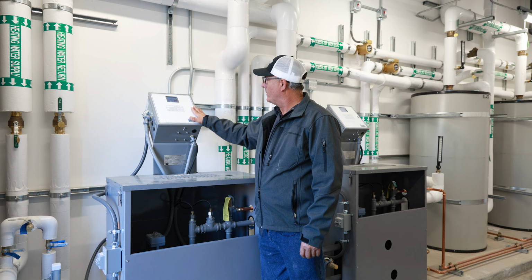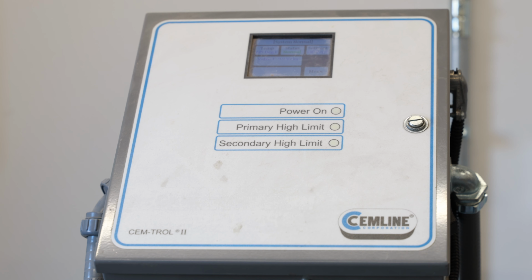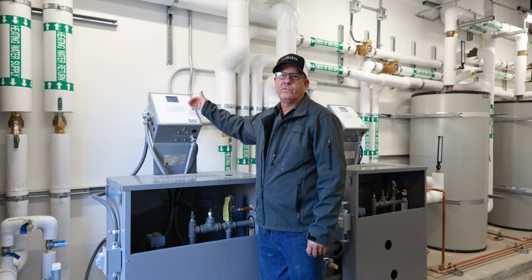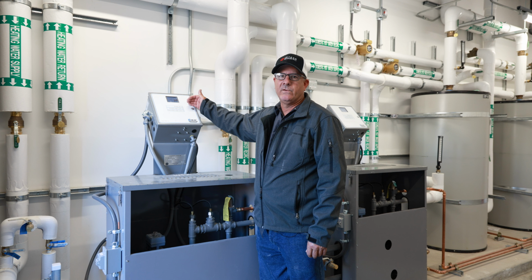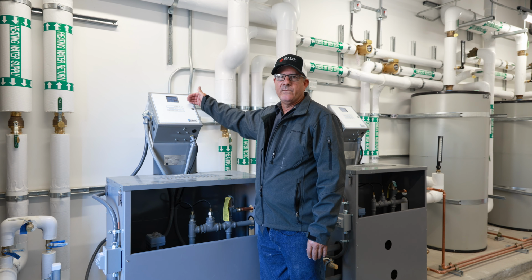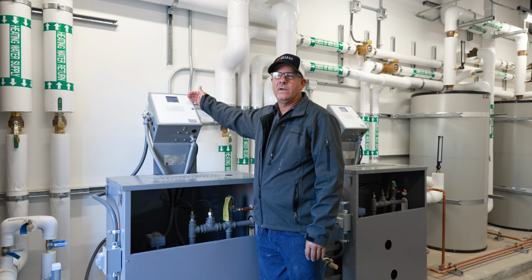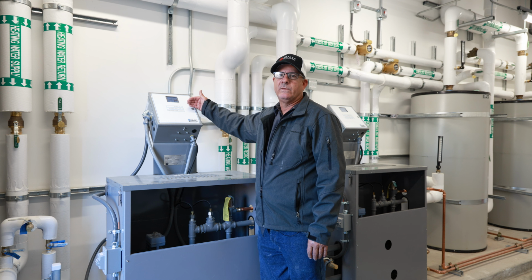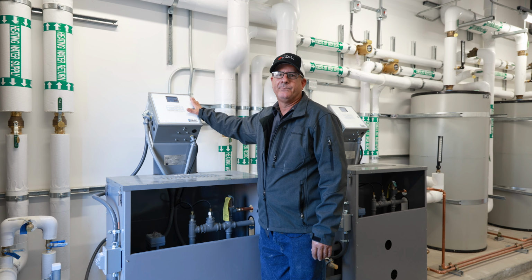Moving up to the controller, this has a primary high limit, a secondary high limit. Those limits are set 10 degrees apart. So 10 degrees above set point, you'll get a limit alarm. 20 degrees above, you'll get the secondary alarm. As the alarms go away, you'll see the secondary drop, you'll see the primary drop, everything will go green.